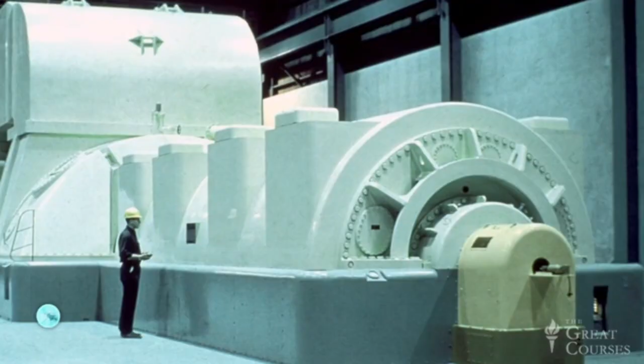This one, a significantly smaller generator called the exciter, is driven by the same shaft as the main generator, but its rotor uses permanent magnets, like the one in my model, and thus doesn't rely on an external source of electrical power. Meanwhile, back at the power plant, the electricity produced by the main generator is transmitted to this adjacent switch yard, where a small portion is diverted back into the plant to drive pumps, conveyors, lighting, and such. The remainder begins a long journey that will eventually culminate in your home, a journey that we too shall take in our later lectures on power transmission and distribution.